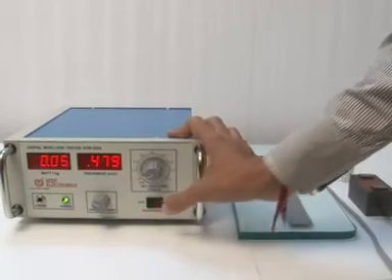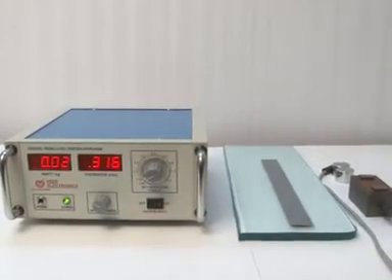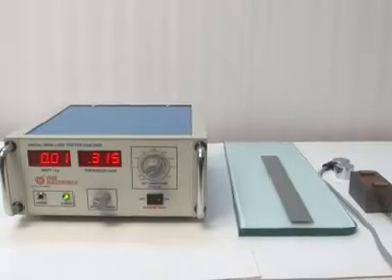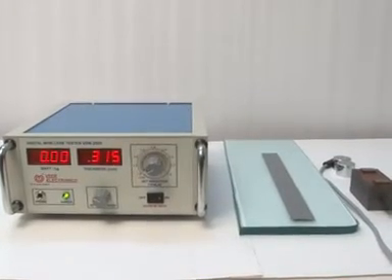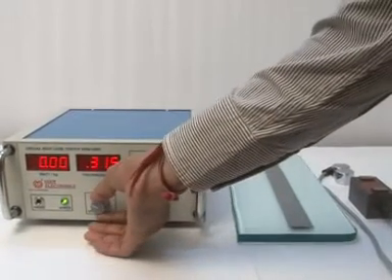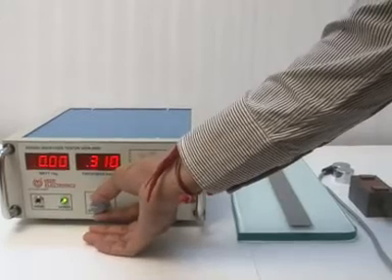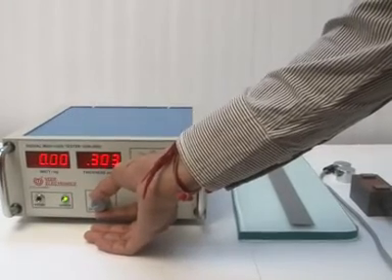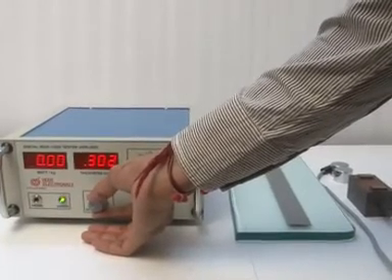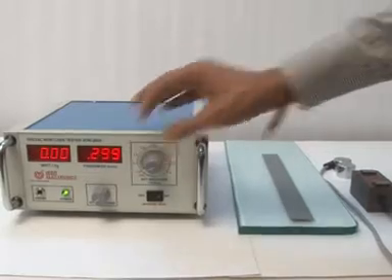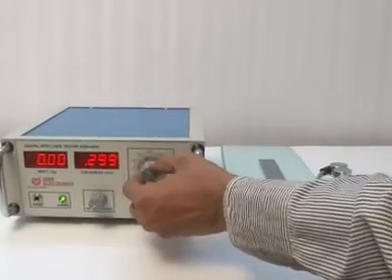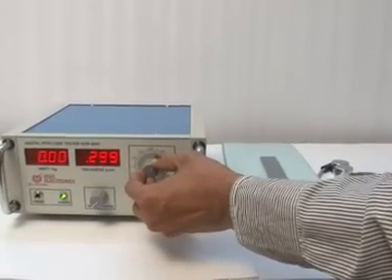Switch on your digital iron loss tester VDW 2065. First, set the thickness of the material using this knob. Now set the induction as per your requirement.